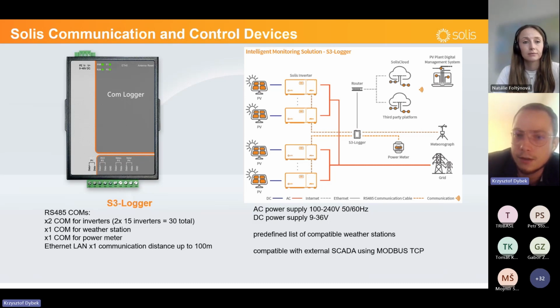So you can use this S3 logger with power meter for more than 20 inverters on site if you need to have power limitation or zero export limitation. It can be connected with 30 inverters on 2 COM ports combined. So you can have 15 inverters per COM port. Next two are for weather station and meter.